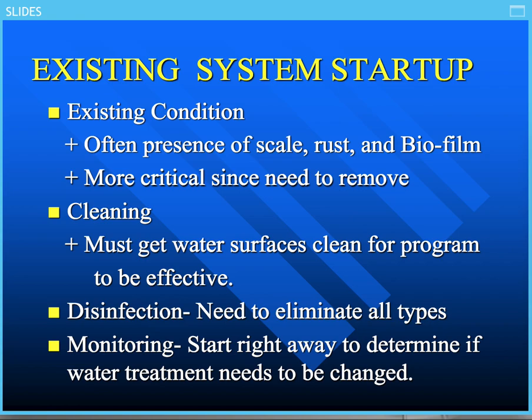When we're dealing with the startup of an existing system, we're dealing with something very interesting. Sometimes people say, well, we'll just get started with what we have right now. The existing system, if you take it over from somebody else, could have a lot of scale, rust and biofilm present. If it does, this has to be removed, because remember, the water is carrying the inhibitor program to the areas you want protected. If you can't get those areas clean enough so that the inhibitor program can get to the surfaces, it's not going to do its protection of your equipment.